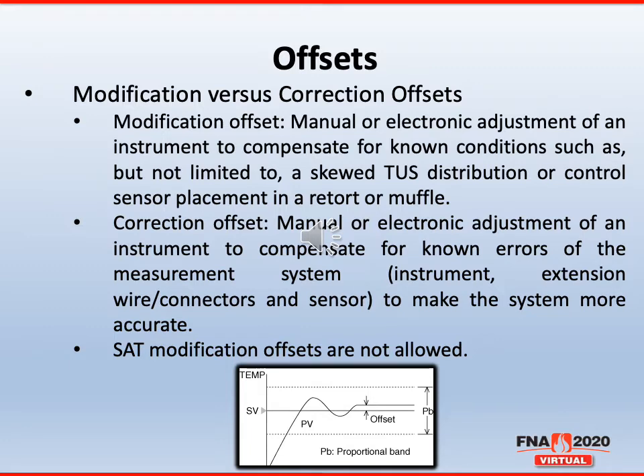We also mentioned that SAT modification offsets are not allowed. So in other words, if you have a failed SAT sensor, you won't be able to use a modification offset to compensate for the failing thermocouple. You will have to replace the thermocouple and retest.